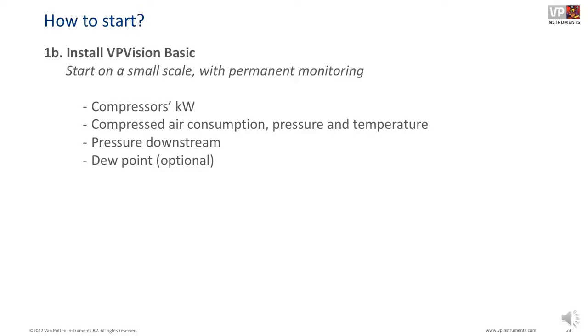So start on a small scale with permanent monitoring. Measure your compressors. It's important because that's where the energy is being consumed. Then look at the air consumption, the pressures, the temperatures, the pressure downstream. Make sure you get an idea of how much pressure you need when you supply the air and how much pressure you have left when it's being consumed. You want to have a minimum pressure drop over the two. And optionally, you can go for dew point. Dew points can be very important for certain processes that are affected when there's moisture migration. So just don't rely on the information coming from your dryer alone. Make sure you build in a redundancy further downstream.